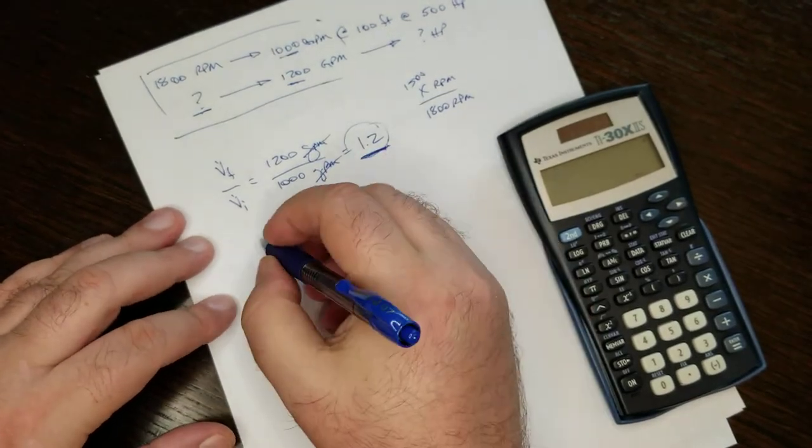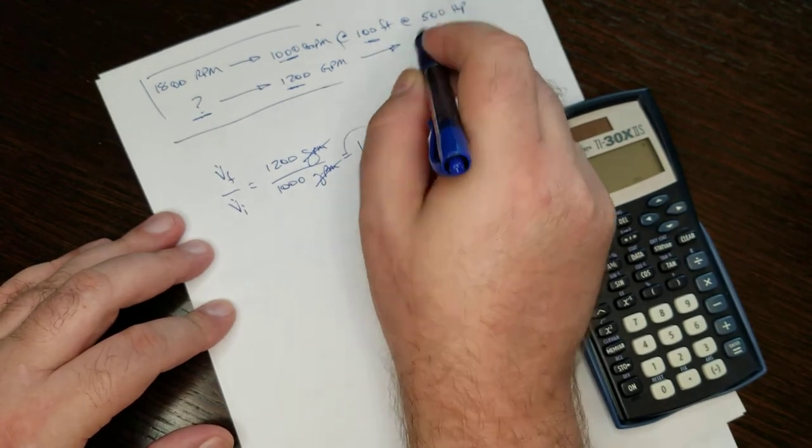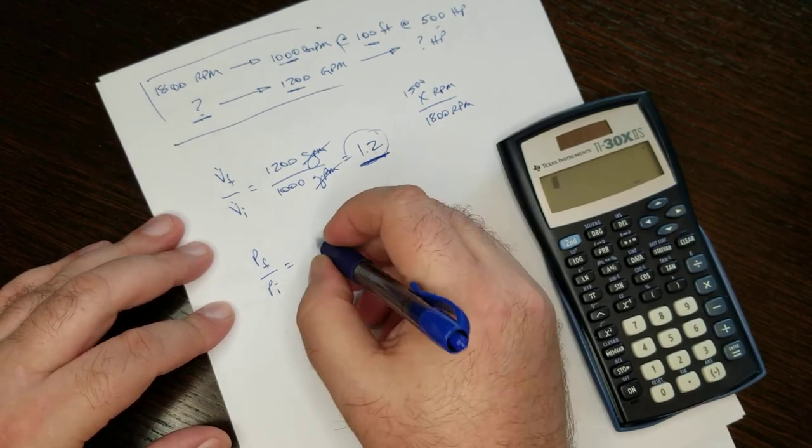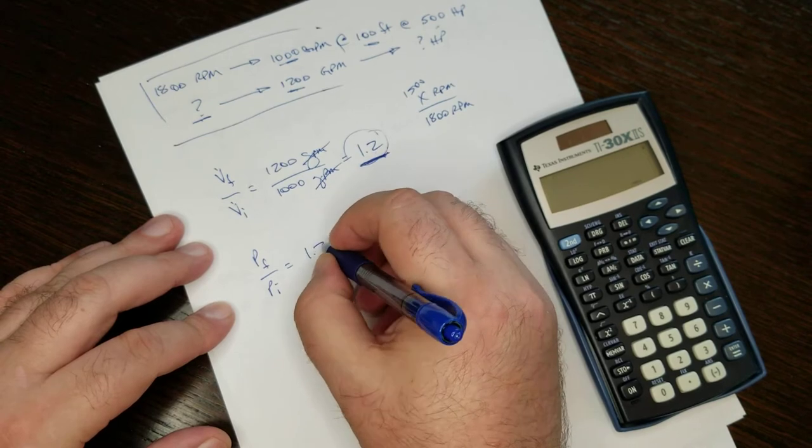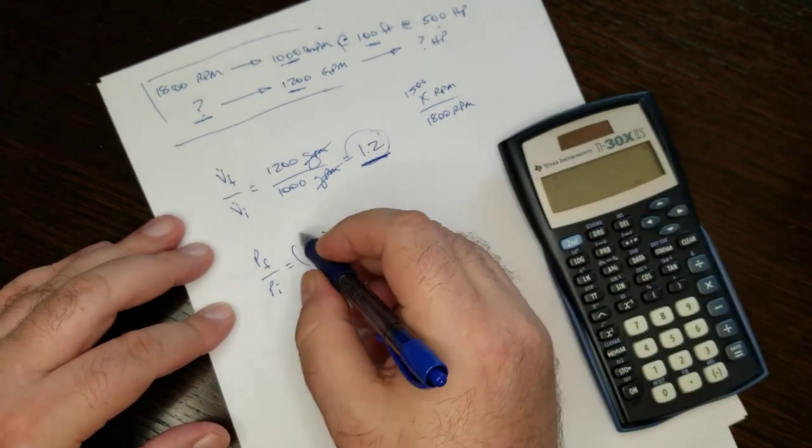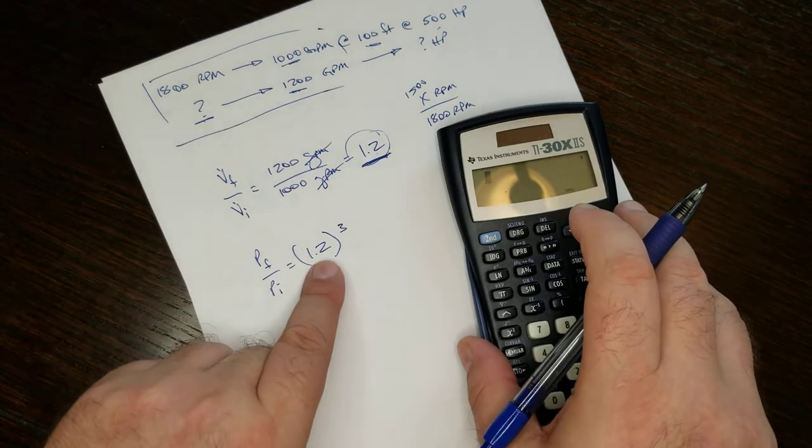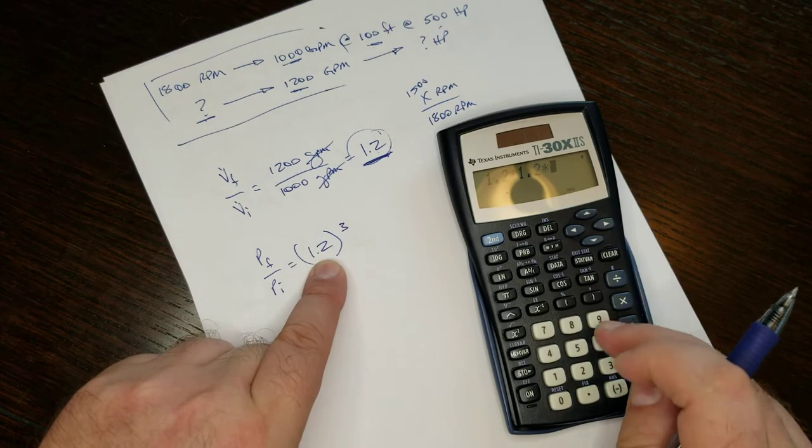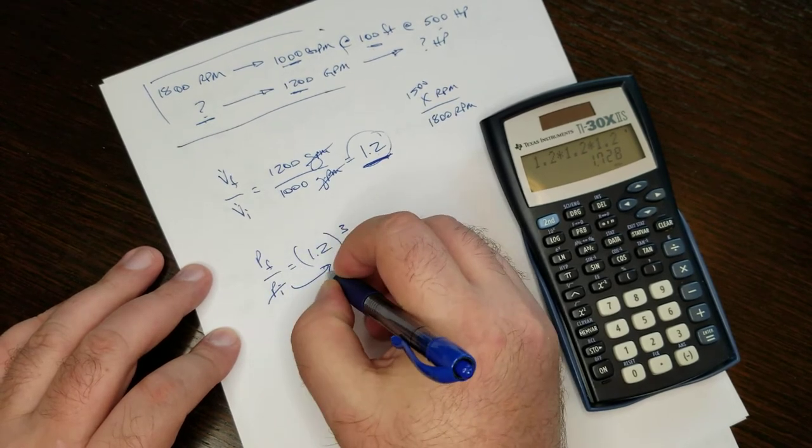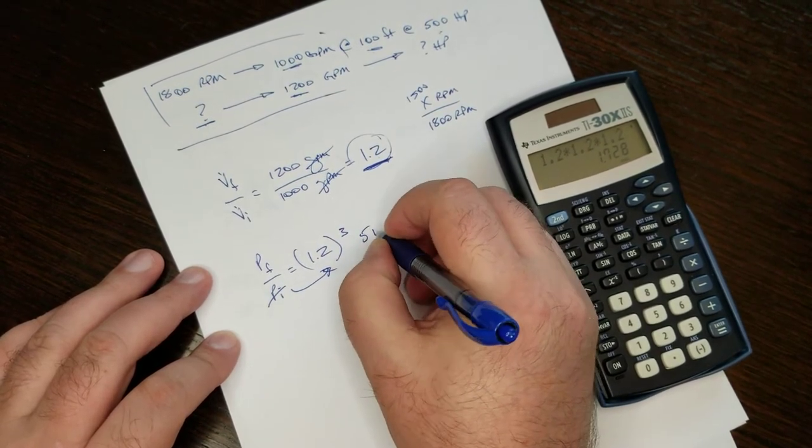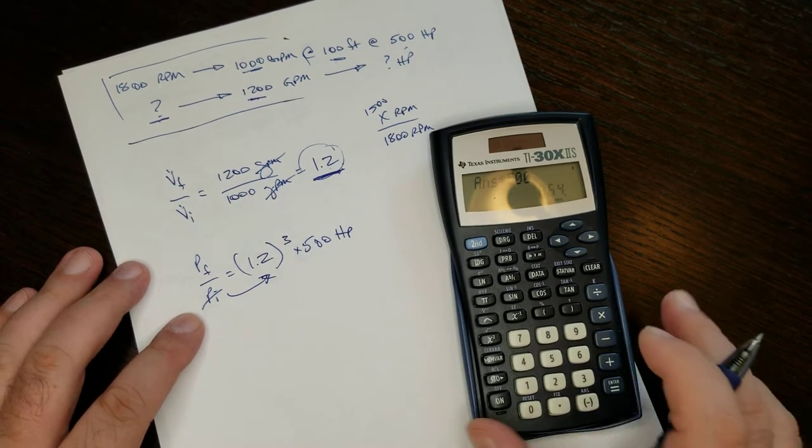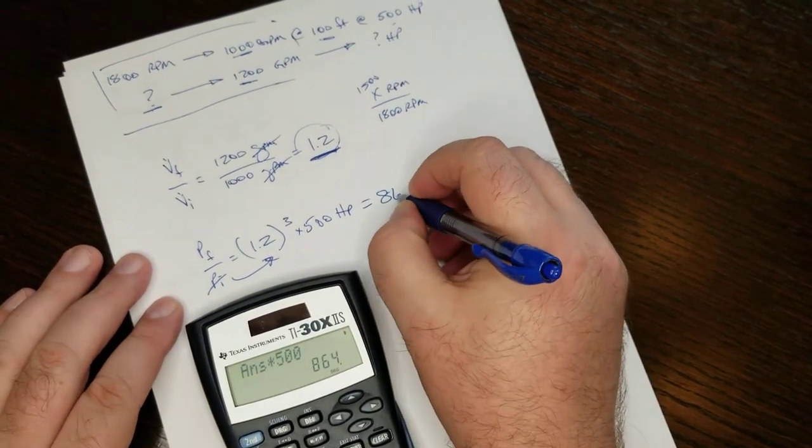I have the 1.2 and we're not looking for pump head. We're looking for power. And so power final over power initial is equal to 1.2 cubed. This is the factor. This is the final over initial speed and we substituted flow rate. You end up with the same value. So 1.2 times 1.2 times 1.2. We're going to move this over here. Our initial power is 500 horsepower times 500. The answer is 864 horsepower.